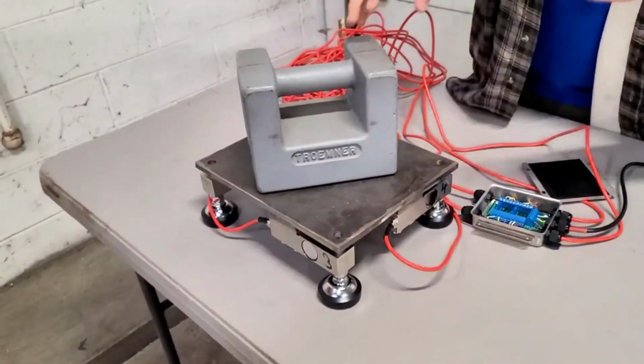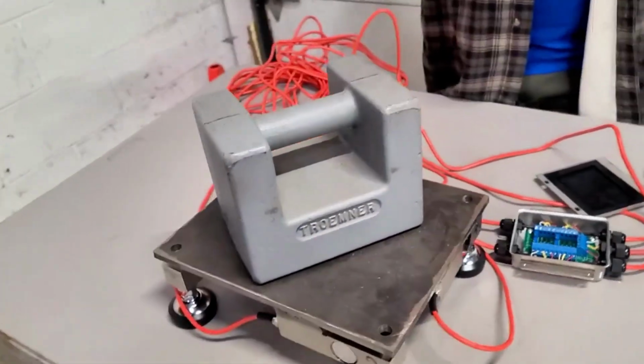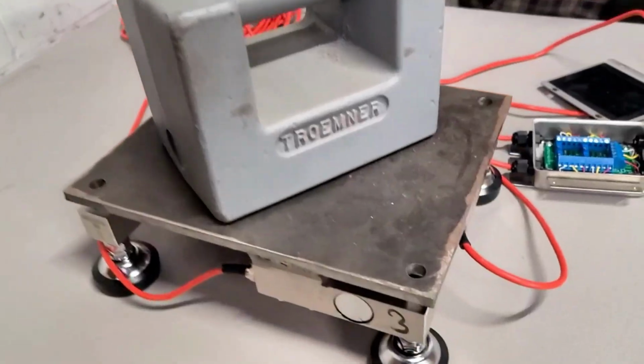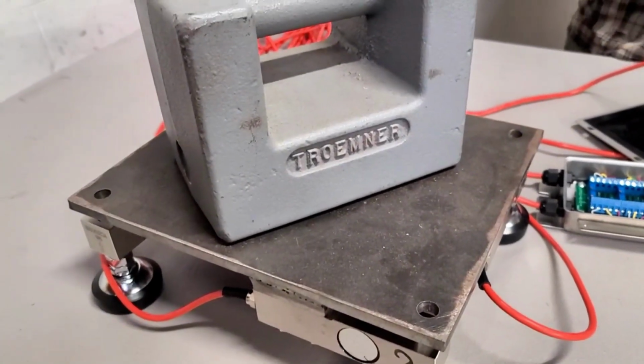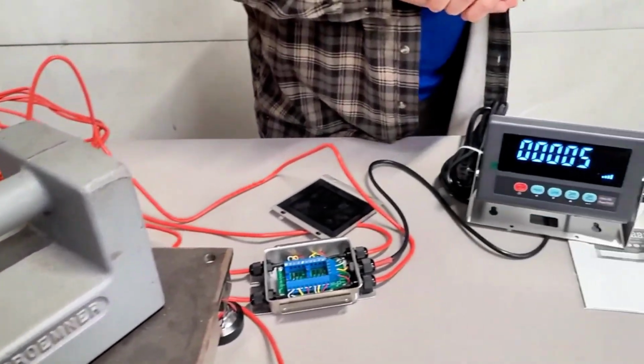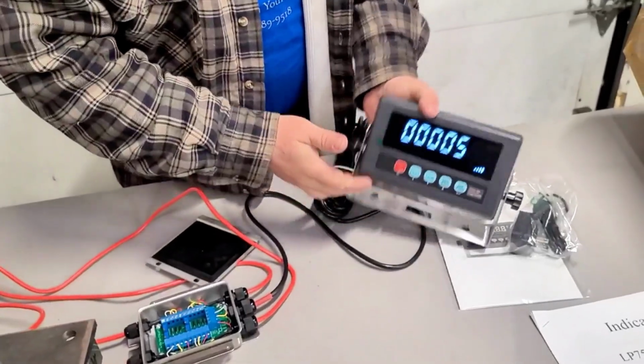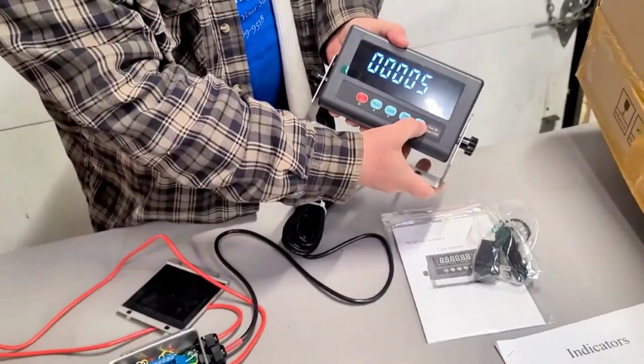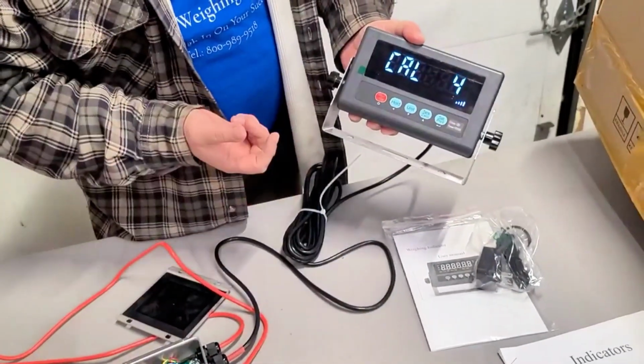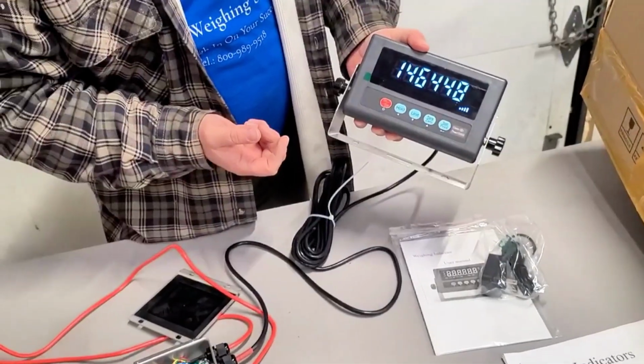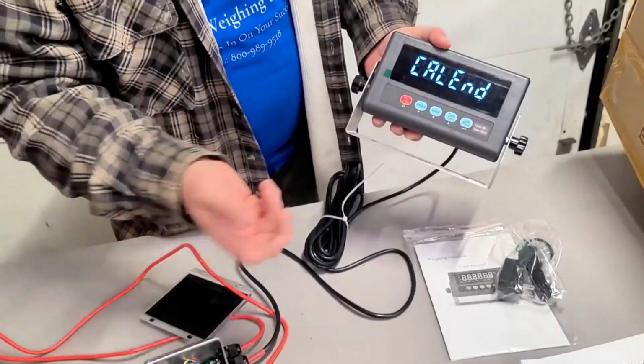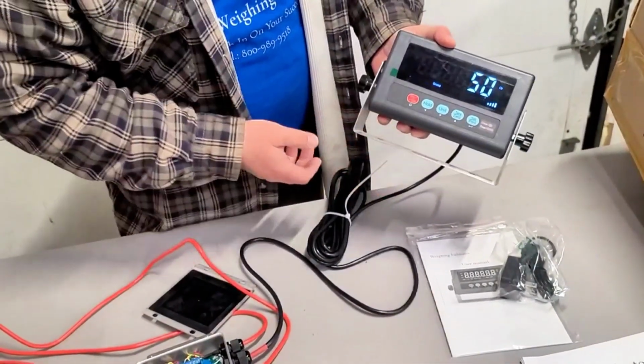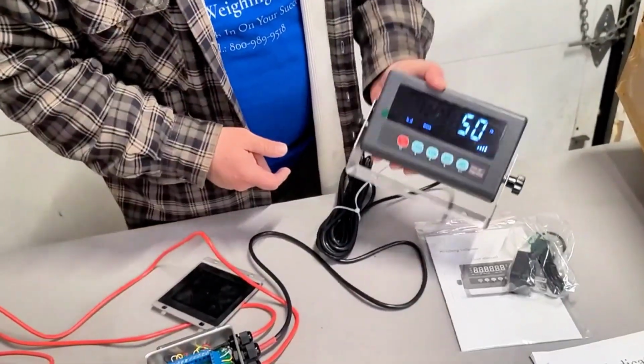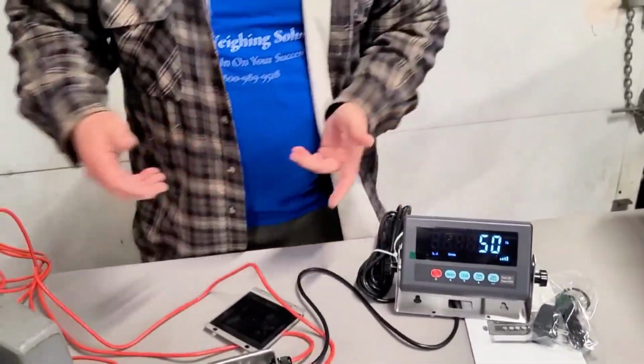You can put a test weight on it, or if you don't have it, you can use something with a known weight. It could be a 50-pound feed bag, for example. Press set, the indicator will count down, and it tells you the calibration ended. Press the on and off button, and it tells you, yeah, you have 50 pounds on it. From this point on, the indicator is calibrated.